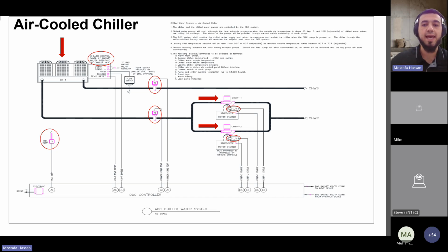Now, I mentioned lead lag, and there's going to be lead lag software for units having multiple pumps. It looks like they want to run lead lag, meaning one pump will run and the other one will wait unless needed, or they'll trade depending on the runtime of one specific pump. Or if the lead pump fails, then the other one will be commanded. And there's going to be an alarm that's going to come back to the operating workstation.